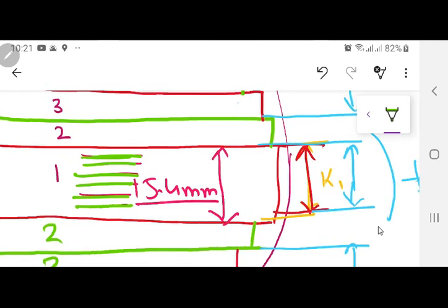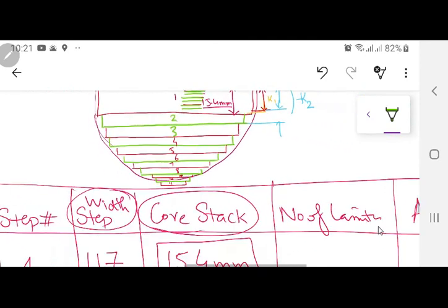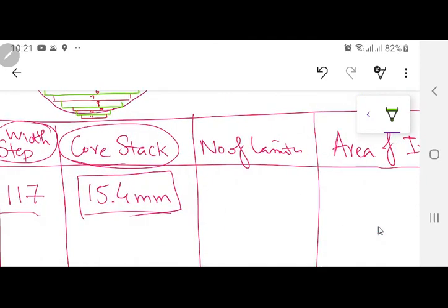So what thickness of lamination should we take? This is totally a factory problem, because the lamination thickness is going to be decided. So over here I am going to take 15.4 divided by, now here it's totally up to you, since each lamination thickness is 0.3 supposedly. Okay? 0.3, and you are going to have an insulation added over there. Maybe that thickness of the insulation is 0.05.